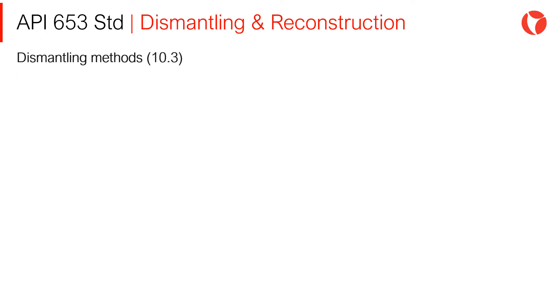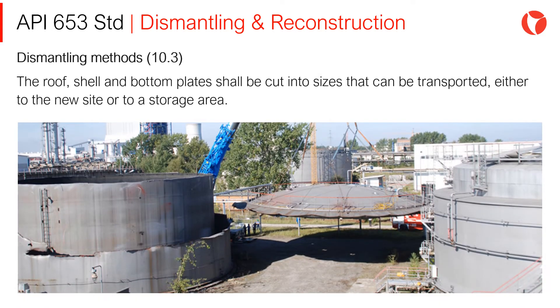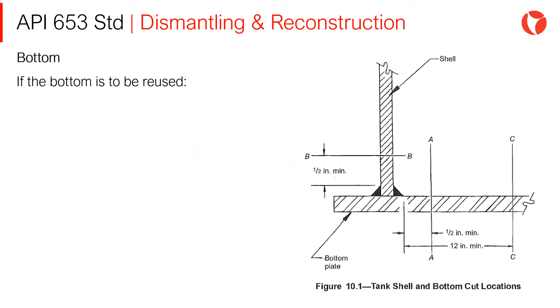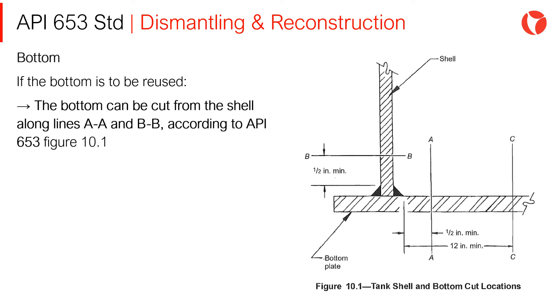Dismantling Methods: The roof, shell, and bottom plates shall be cut into sizes that can be transported either to the new site or to a storage area. Regarding tank bottom dismantling, if the bottom is to be reused, it can be cut from the shell along lines A-A and B-B, according to API 653 Standard Figure 10-1.